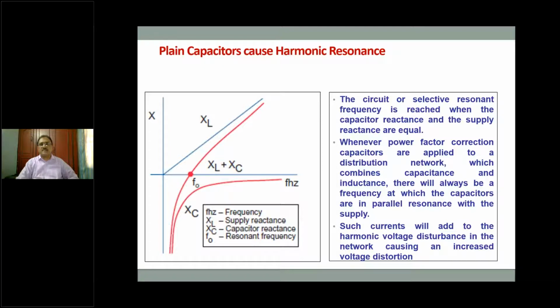If you know there are plain capacitors and also many nonlinear loads, those plain capacitors are going to cause an incremental increase in harmonic content, which will go to the grid and also affect you. In Tamil Nadu, it is a penalty when you exceed the limits. In states like Maharashtra now, and most of the North Indian states, like for example Delhi, UP, Haryana, Punjab, Rajasthan, Himachal Pradesh, and down south Telangana and Andhra Pradesh, have already implemented kVAH billing, which is affected by both power factor as well as by the harmonic. So harmonic in that sense is an undesirable element. It will increase your power bill and it will give you losses in the system.